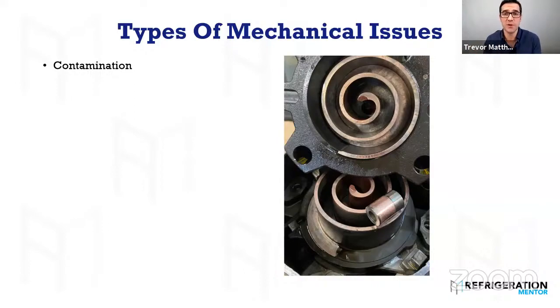So contamination is the first one. There are six types of mechanical failures, and we're not going to dive into electrical failures today, but six types of mechanical failures. Contamination is one of them, and contamination starts from day one installation. If you do not install that system correctly the very first time, you're going to have failures. It might not be in six months, it might not be in one year, it might be two or three or four years down the road because of that day one installation. Number one thing you need to do is make sure there is no non-condensable or moisture inside that system.